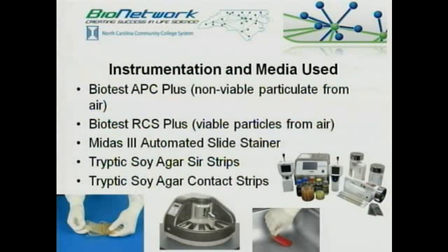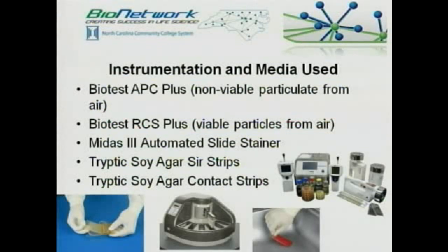Counting 0.5 and 5 micron-sized particles. The Biotest RCS Plus is our centrifugal air sampler, which will sample 1,000 liters of air in 20 minutes. The high-speed RCS Pluses from Biotest Diagnostics can sample that same 1,000 liters—which is, by the way, the required amount the FDA requires you to sample—in just 10 minutes. The MIDAS 3 automated slide stainer has the capability of doing multiple different staining techniques and is programmable to whatever the user desires. The centrifugal air sampler uses a strip made from tryptic soy agar.